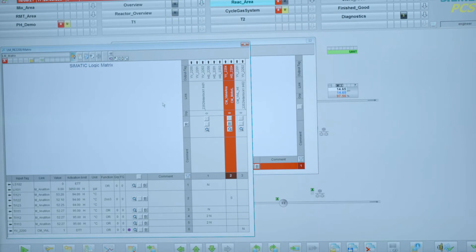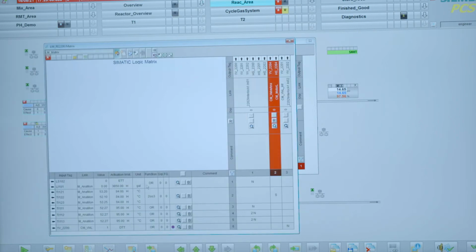So instead of having logic all the way around your application, there's going to be one place where you configure what is the reason to cause an interlock, and that's called a cause. Then on the other side of the matrix, so the causes are listed here horizontally, so you can see the list of causes as inputs. There's the effect. So in case a cause would occur or become true, then one or more effects can be energized or de-energized.